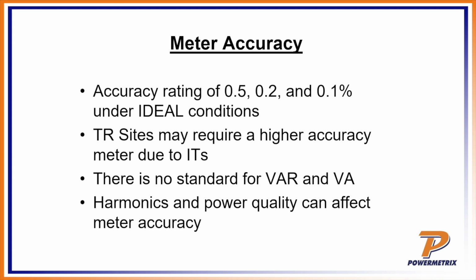If I've got some of those extended range CTs, like 0.15% accuracy CTs, then you see what's going to happen, right? Then I need to make sure that my meter matches up. And there's no real standard for VAR and VA. Harmonics and power quality can affect the meter accuracy. So another consideration is whether this is going to be an installation with a lot of harmonics involved. That's another thing to consider before you choose your meter.